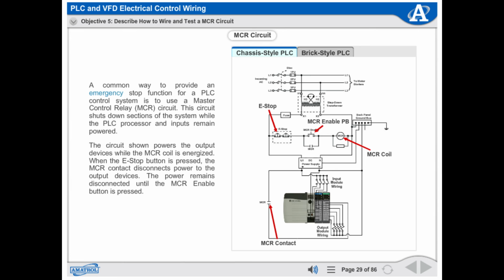The circuit shown powers the output devices while the master control relay coil is energized. When the E-stop button is pressed, the master control relay contact disconnects power to the output devices. The power remains disconnected until the master control relay enable button is pressed.